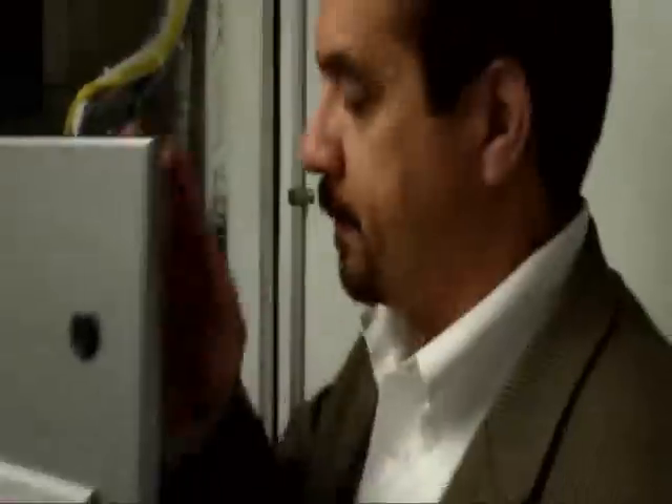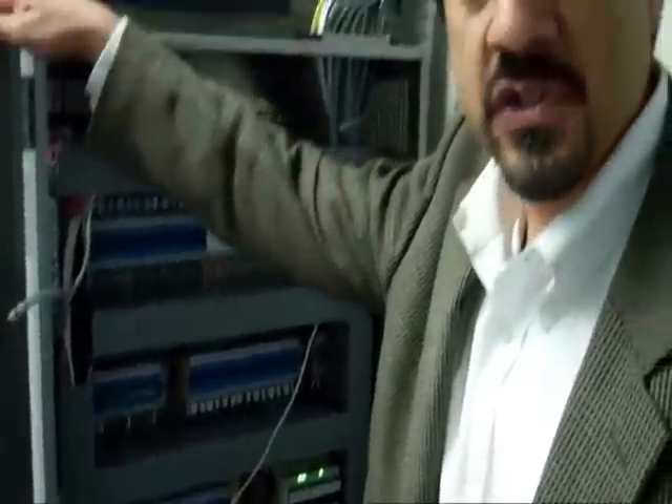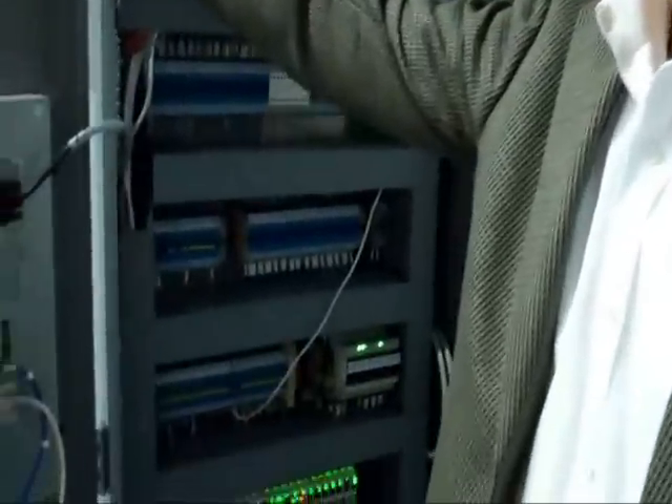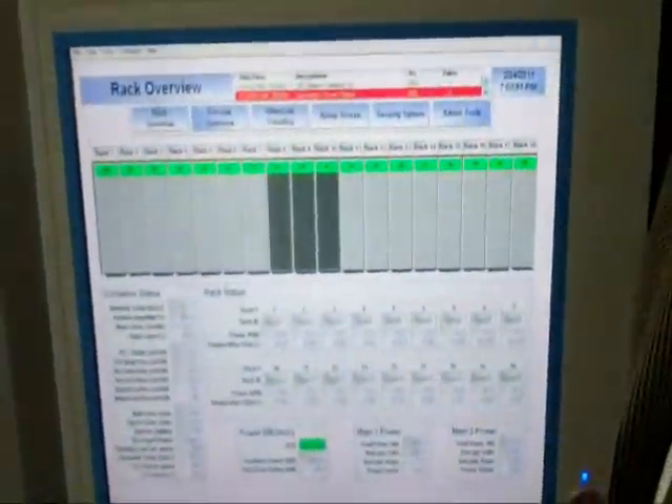The management system is a three-level system. We have a PLC that takes inputs from all sensors and monitors within the container and makes decisions about how to operate it — when to turn on the humidifier, lights, and external air makeup to ensure fresh air. We also have an industrial computer that allows you to take that data, store it, do trend analysis, and do database management. If you want a good database and information about all the equipment in your system, you can store that data in that computer. We also have the HMI touch screen as part of the system.